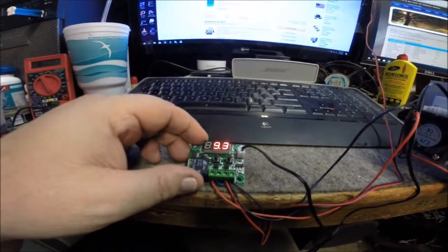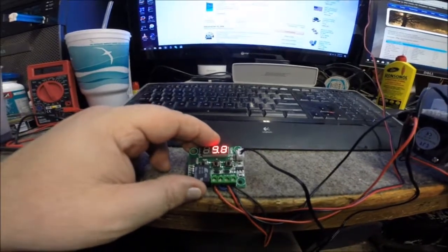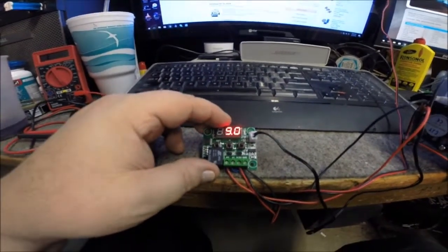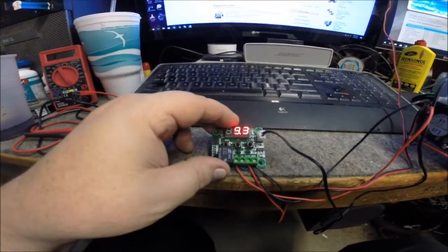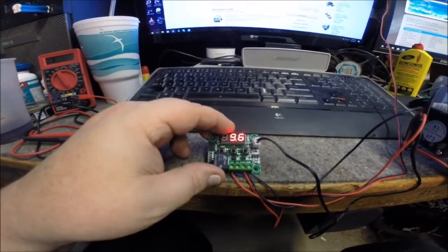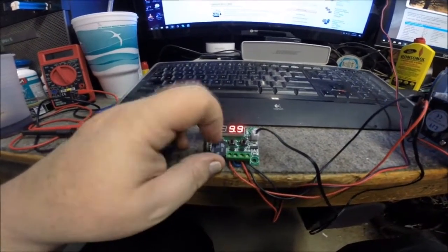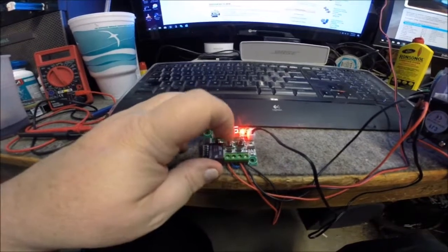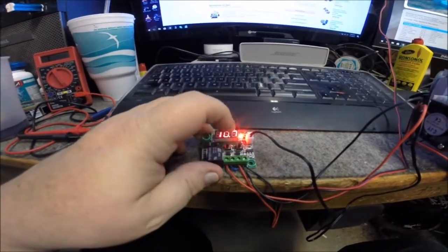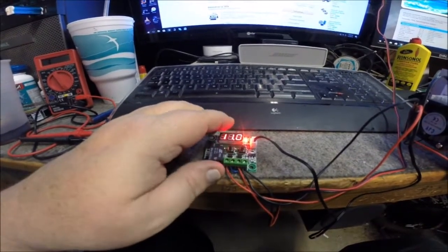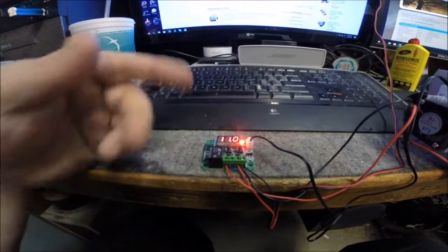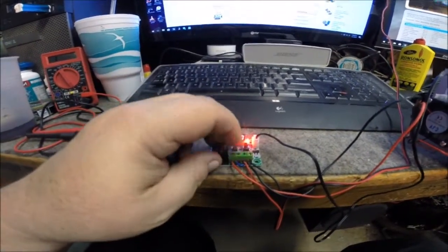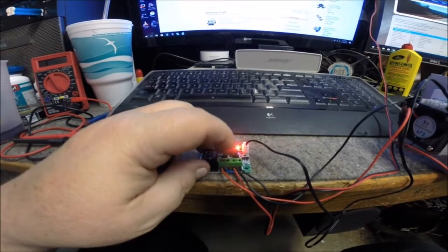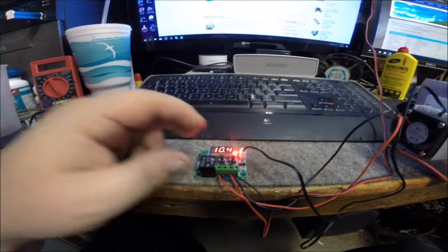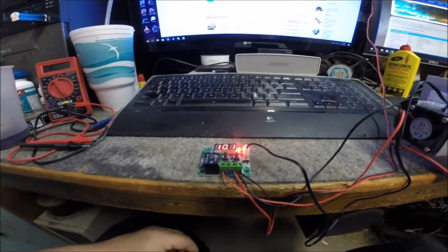Now, this is where it gets a little tricky. You got to understand K0 and K1, that is not power feeds. All that is an open shut circuit. In other words, there's this relay right here, turns off and on via the settings you set here, but it's a shunt, it's an off on switch, and it carries no voltage whatsoever on K0 or K1. So you have to envision it as a single pole switch.